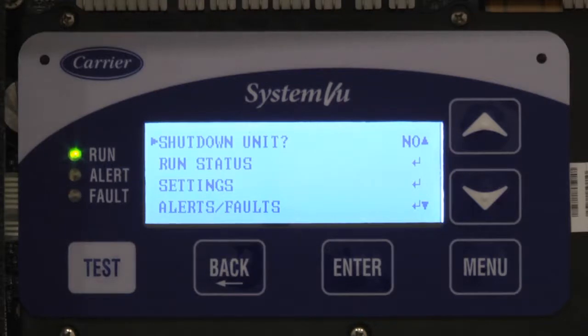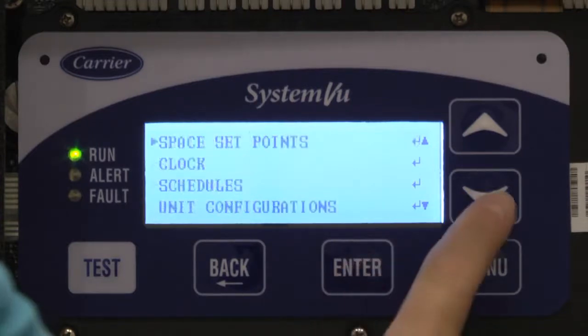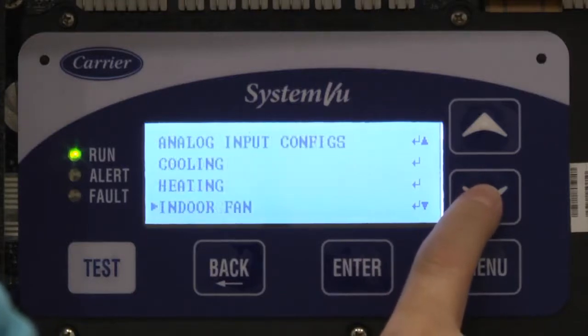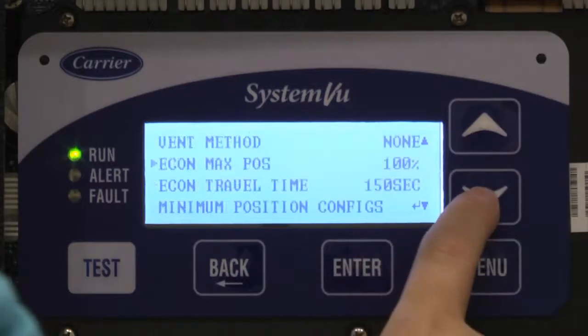SystemVu in general, regardless of variable speed, allows you to set an actual curve for various operating positions, and this is what we'll walk you through. So: Settings, Unit Config, and then Economizer, and then Minimum Position.